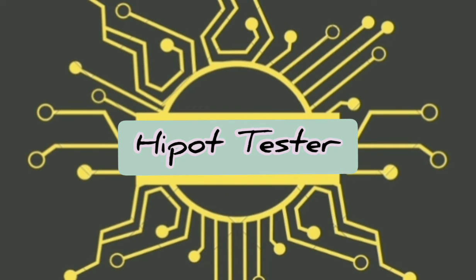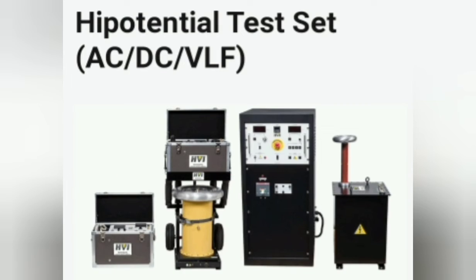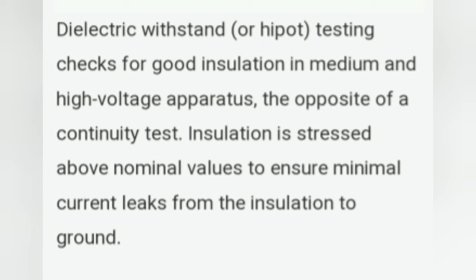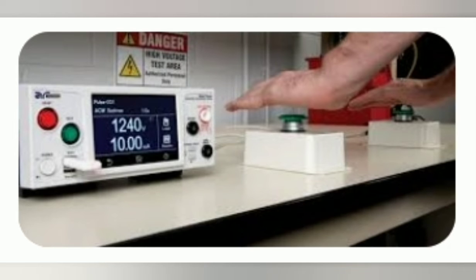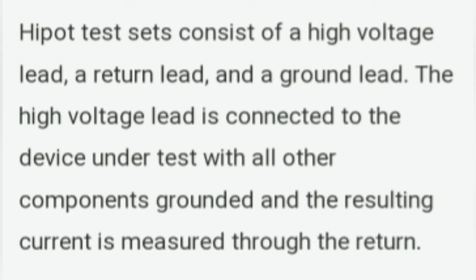Another measuring instrument is the Hipot Tester. Dielectric withstand or Hipot testing checks for good insulation in medium and high voltage apparatus. The opposite of a continuity test, insulation is stressed above nominal values to ensure minimal current leaks from the insulation to ground. Hipot test sets consist of a high voltage lead, a return lead, and a ground lead.